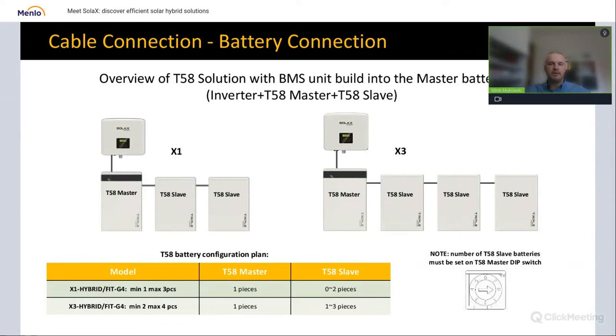So you have to set him on that dip switch. If there's 1 slave, you set him to 1. If there are 2 slaves, you set him to 2. If there are 3, you set him to 3. Sorry, and so that's important - before you turn the battery on, you have to set the proper number of slaves used in the system you just installed.